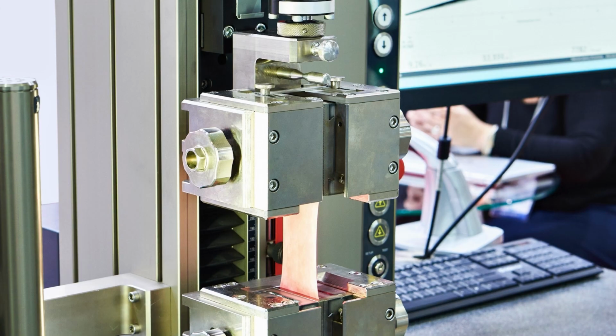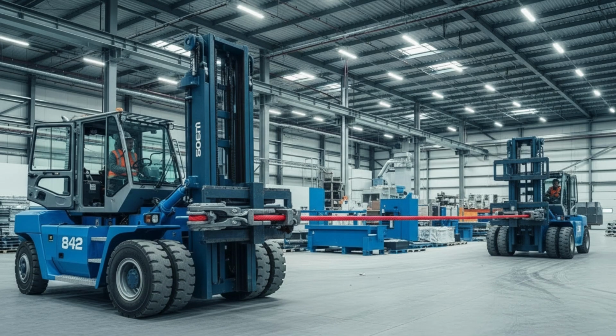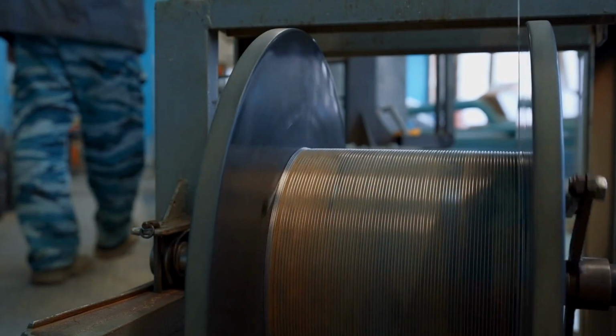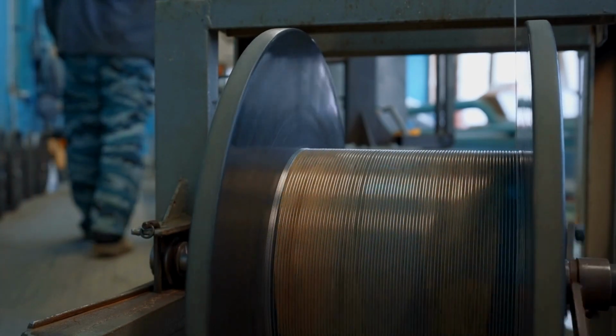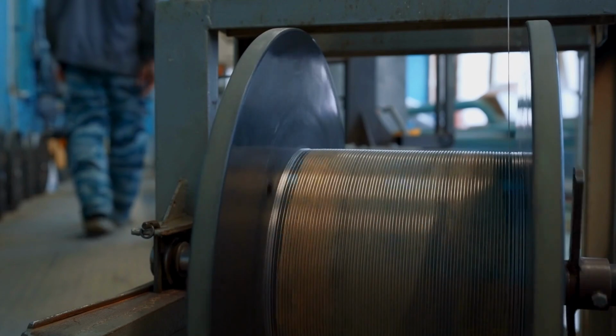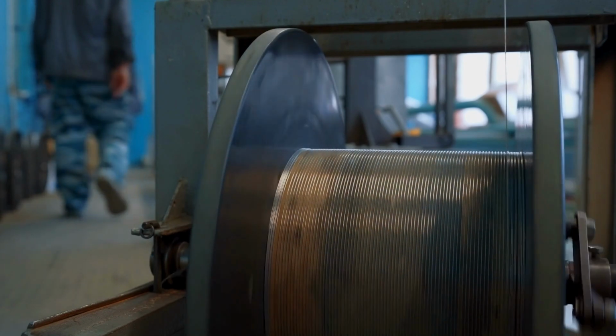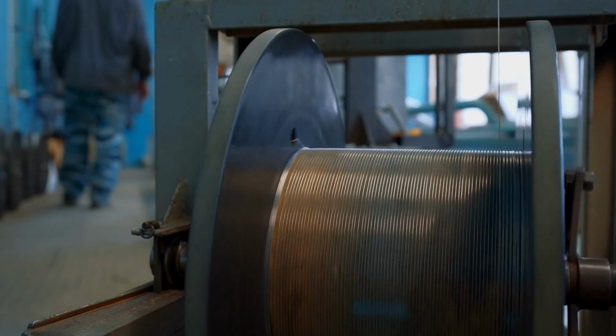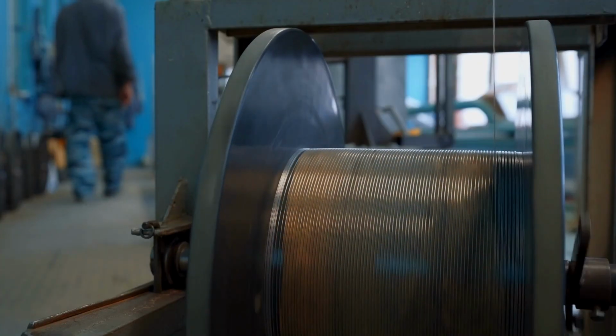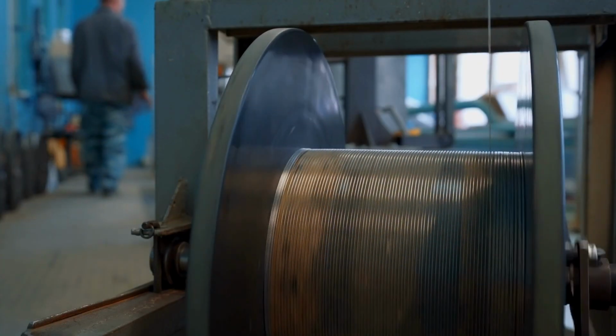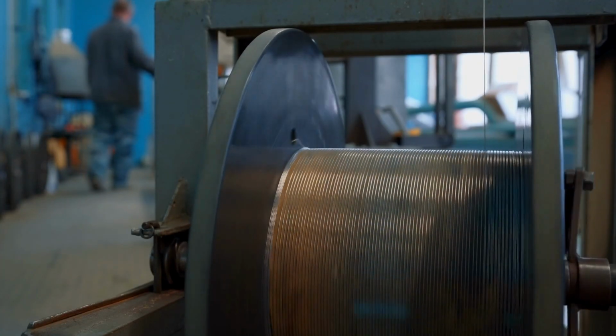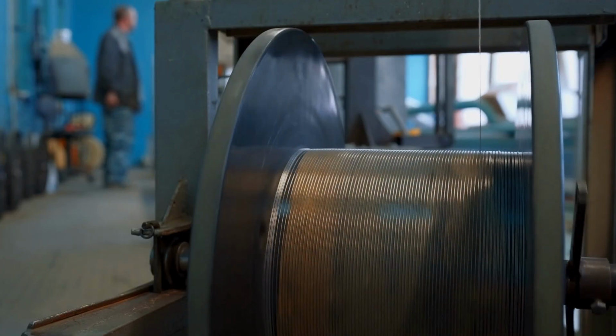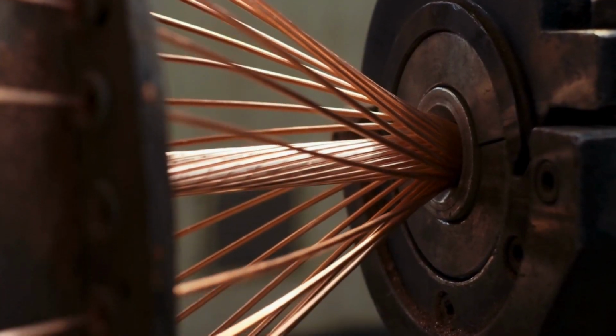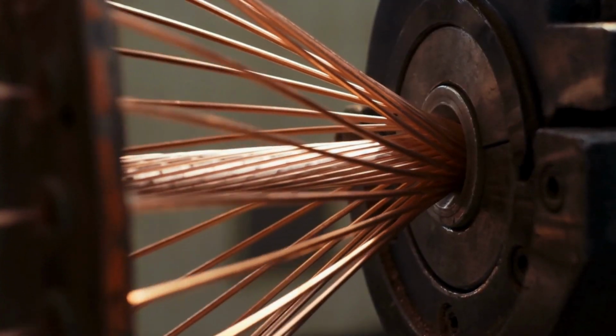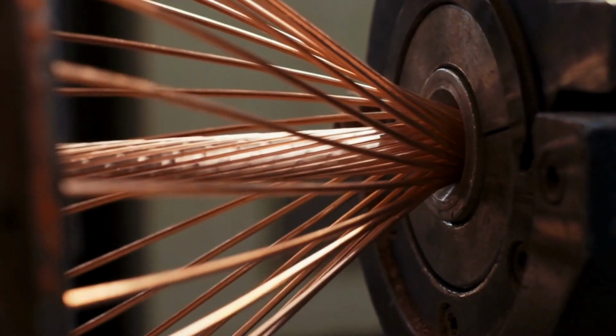Throughout the entire production process, continuous testing is performed to detect defects as early as possible. One of the most common online tests is the spark test. As the wire passes through high-voltage electrodes, any pinhole or abnormally thin insulation area immediately produces a spark, indicating a defect. When a defect is detected, the system can trigger alarms, mark the faulty section, or automatically stop the production line. This ensures that defective wire is removed before it reaches the customer.